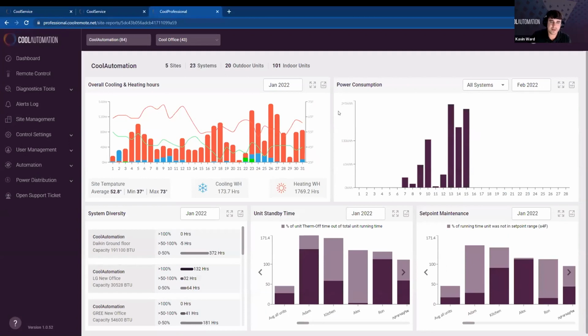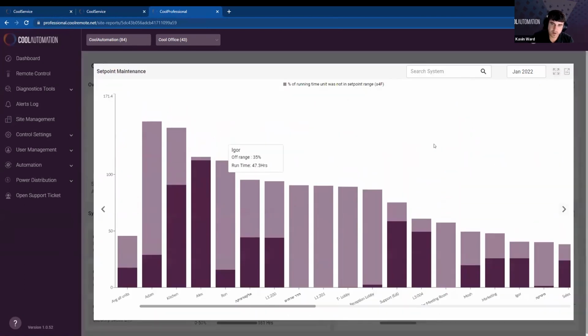Another feature of our app will be a simplified report section where you can quickly analyze the performance of your site. Here you can see a breakdown of the overall cooling and heating hours, power consumption of your system, how hard your system is working with the system diversity, how often your systems are actually calling for heating or cooling, and as I mentioned, set point maintenance. This will give you a snapshot view of how well your system is actually satisfying set point at your site.